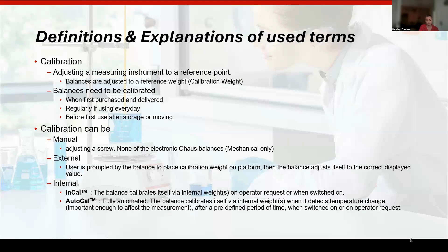We've also got a feature on some of our balances, which is AutoCal, which is fully automated. The balance will calibrate itself via the same internal weight, but it will do it automatically when it detects a big fluctuation in temperature, which is important enough to affect any measurement. You can have it set to calibrate itself after a predefined length of time, or upon operator request, or when it's switched on. So with the electronic balances with AutoCal, you can set it depending on your preference.